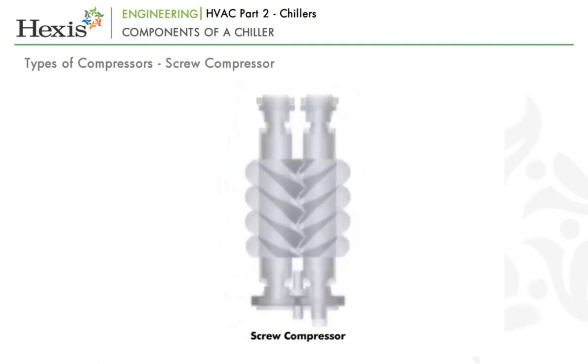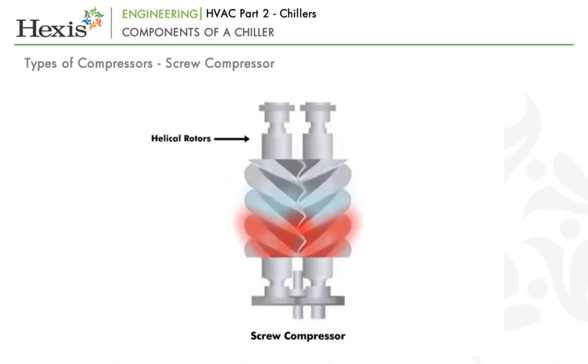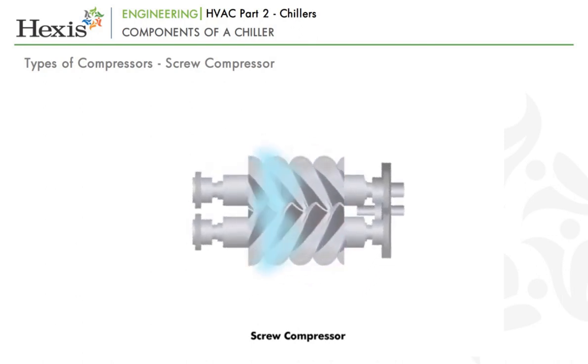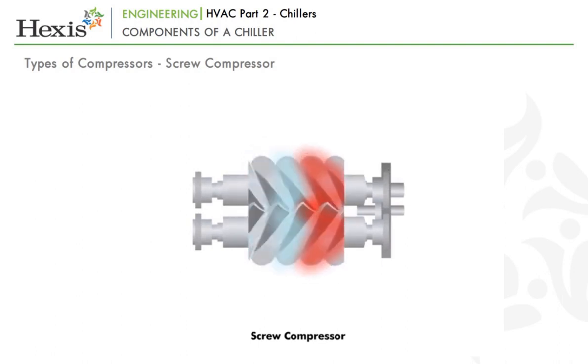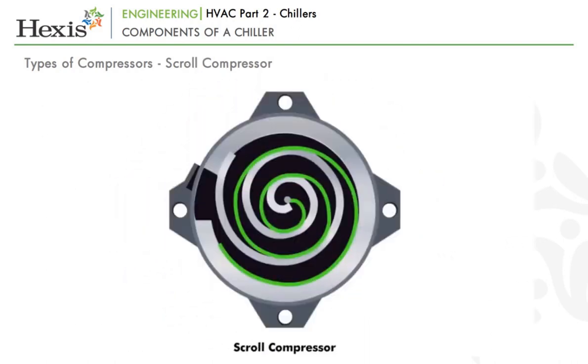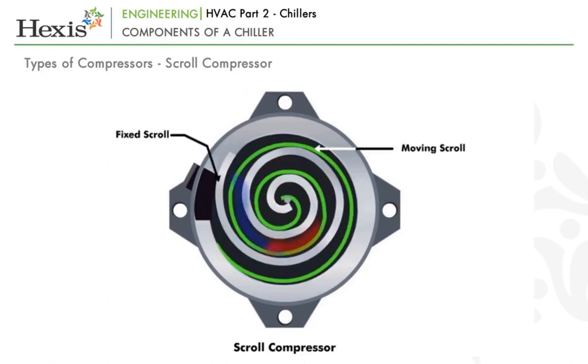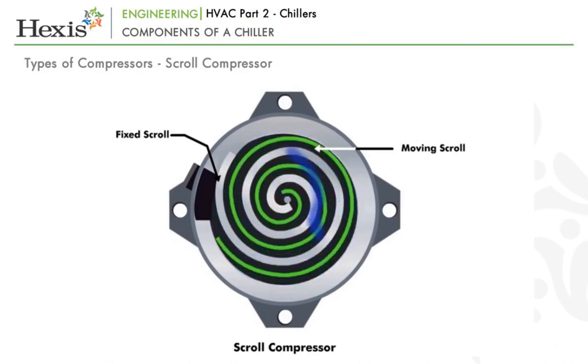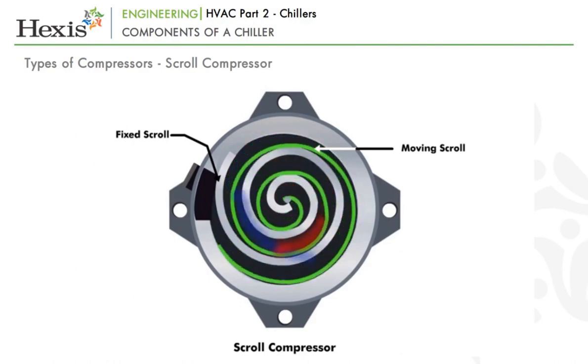Screw compressors use two helical rotors which mesh together to trap and compress the gas as it moves forward towards the outlet in a cylinder, with the available space getting increasingly smaller. They have increased reliability due to fewer moving parts and higher efficiency. The last type is the scroll compressor, which comprises two scrolls — one fixed and the other moving. As the moving scroll moves, pockets of gas are slowly moved towards the center, gradually reducing in volume, thereby compressing the gas.